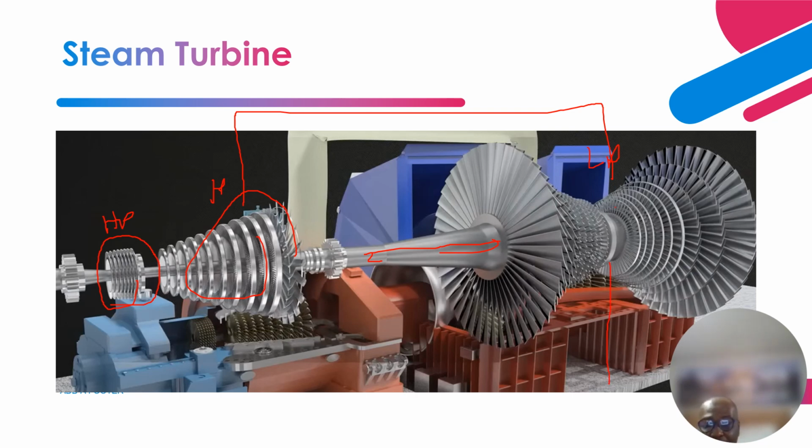Then from here, it comes down into a condenser. The steam collapses, they call it. That is the technical word they use. The steam collapses into the condenser. Once it gets into the condenser, it is about 70% saturated with water and 30% steam. And it gets into contact with the cooling water that flows in the walls of the condenser, which also has a closed loop pipe cooling with cooling water. So once the steam gets into contact with it, it forms pure water.